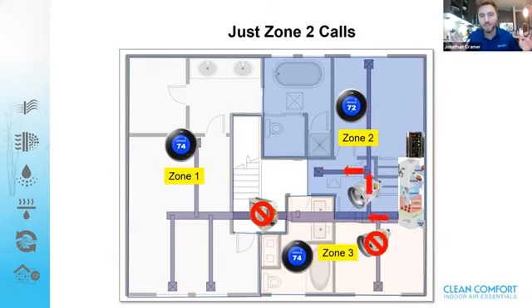But then zone 3 said, you know what, this is just a little too loud. I'm just going to shut it off. I'm good at 74. I don't really need to be satisfied right now. So now zone 2 is like, well, I still want 72 degrees. So now those dampers are completely closed. We are blocking airflow from going to either zone 1 or zone 3, and only zone 2 is getting airflow. So can you imagine what it would feel like if you were in zone 2 right now? I'm sure if you had papers on the desk, they would be moving, they'd be flying around. You'd be hearing a lot of noise that you're not used to hearing.